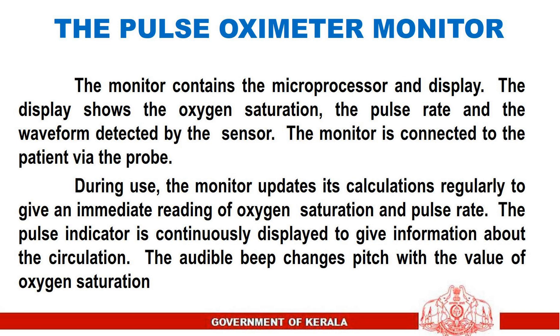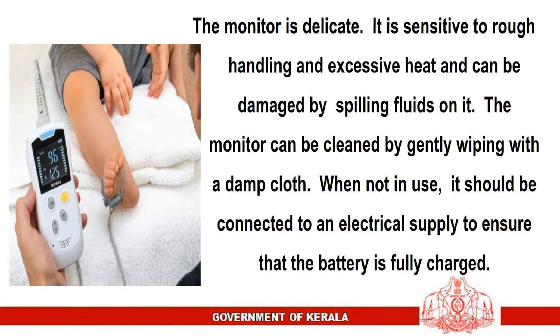During use, the monitor updates its calculations regularly to give an immediate reading of oxygen saturation and pulse rate. The pulse indicator is continuously displayed to give information about the circulation. The audible beep changes pitch with the value of oxygen saturation. The monitor is delicate — it is sensitive to rough handling and excessive heat, and can be damaged by spilling fluids on it. It can be cleaned by gently wiping with a damp cloth, and when not in use should be connected to an electrical supply to ensure the battery is fully charged.